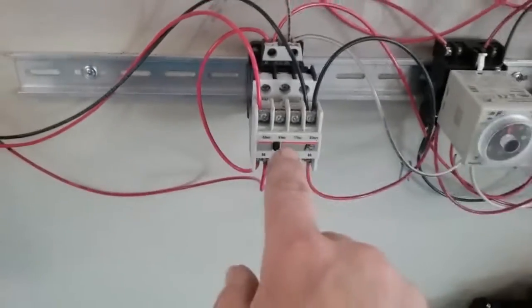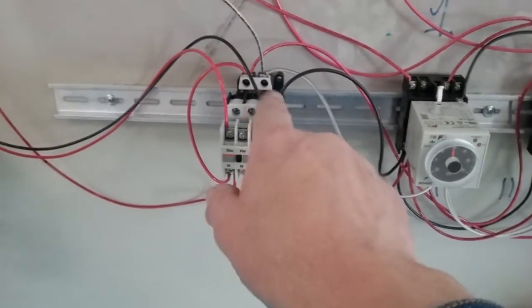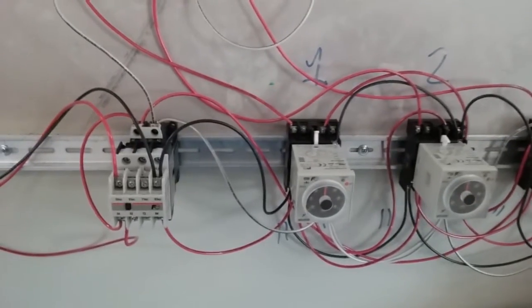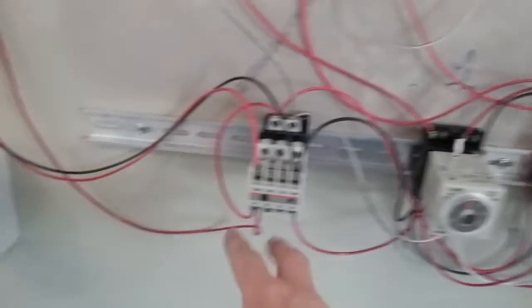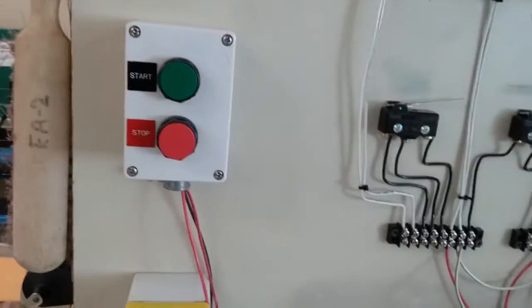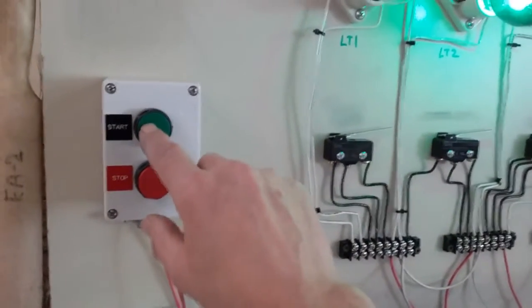What this contactor does is two things. First of all, it sends the power to the control for the timers. Second of all, it acts as a holding relay so that I don't have to sit here and hold the start button down. That doesn't happen automatically - that's a momentary contact switch inside the start button. We use the contactor to latch that switch using magnetism to accomplish that.